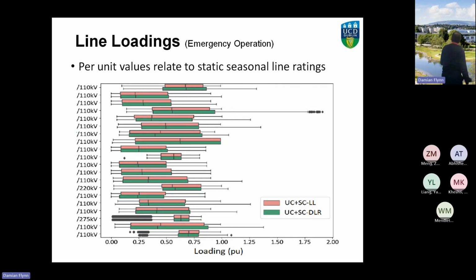We also did something similar for emergency operation. What if we have our intact network, then we lose a line? What will be the impact on the neighboring lines? It will tend to increase the loading. So if we consider an N-1 case, you can see more lines going beyond 1 per unit, hence the advantages of short-term overrating or dynamic line rating.